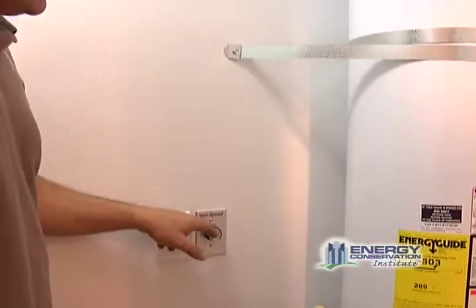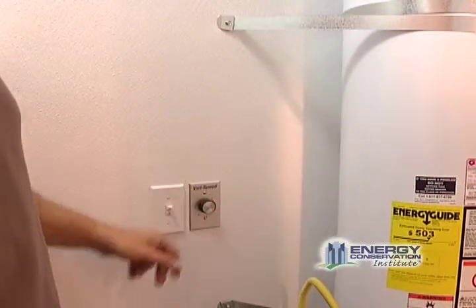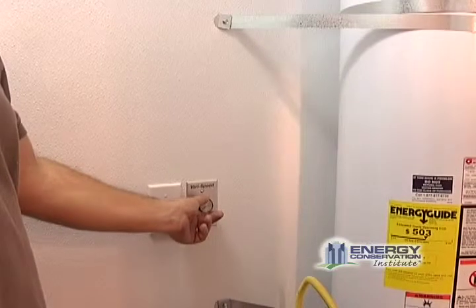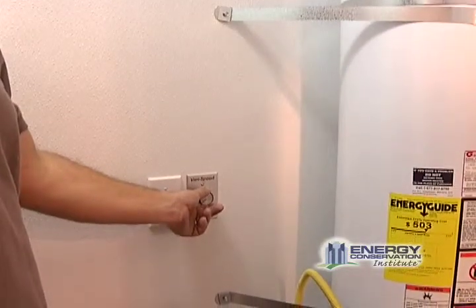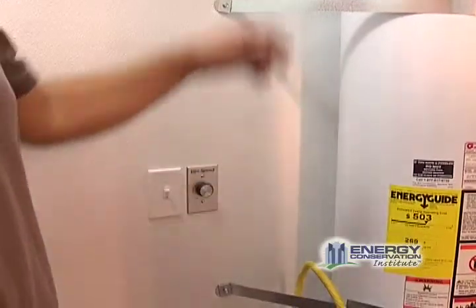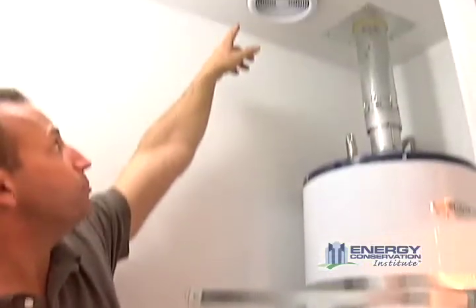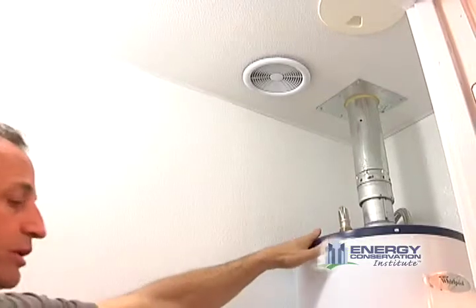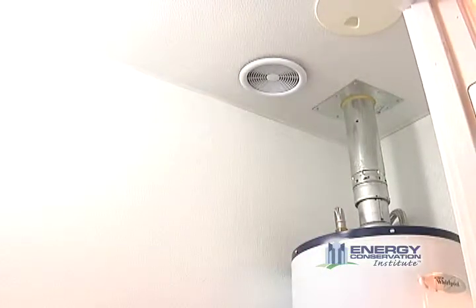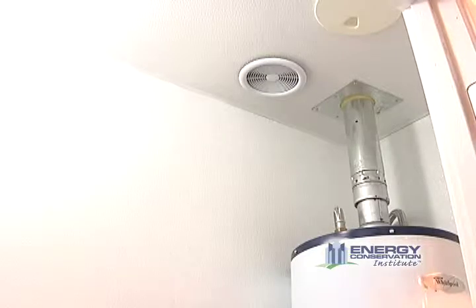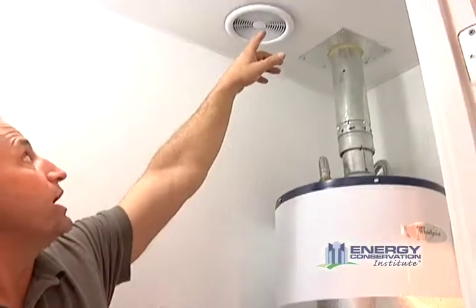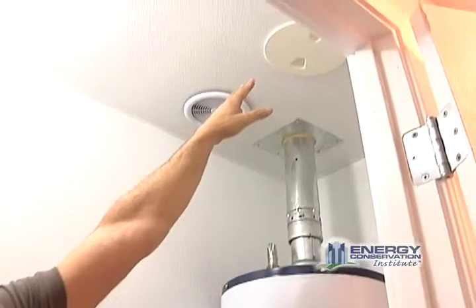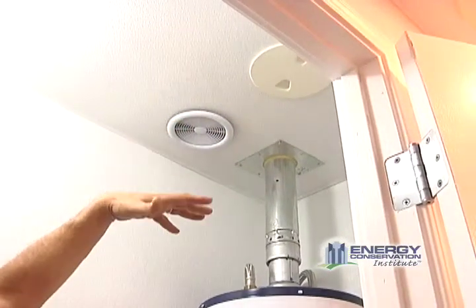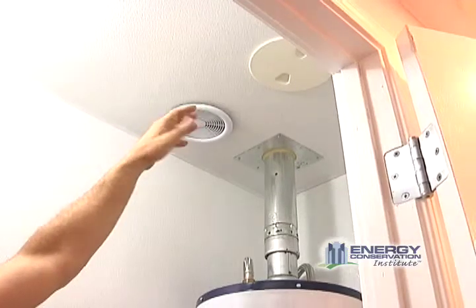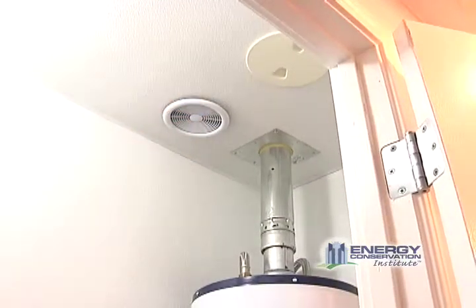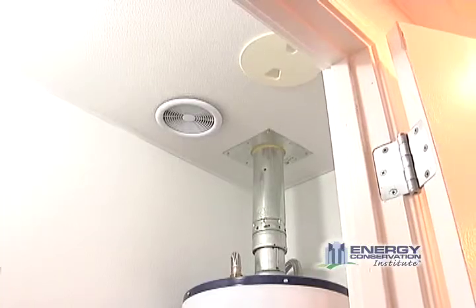You'll also see that we've got an adjustable speed exhaust fan here. This is great because you can adjust the exhaust from approximately 50 CFM to 110 CFM, and the exhaust fan is located right here above the water heater, so it's great for showing how too much negative pressure can affect your draft. You'll also notice up here, just to the right of your exhaust fan, is one of the leakage ports that I showed earlier. So if we want to create a leak in this room through the attic space, we would simply remove that port. Now let's take a look at the other side of the laundry room.